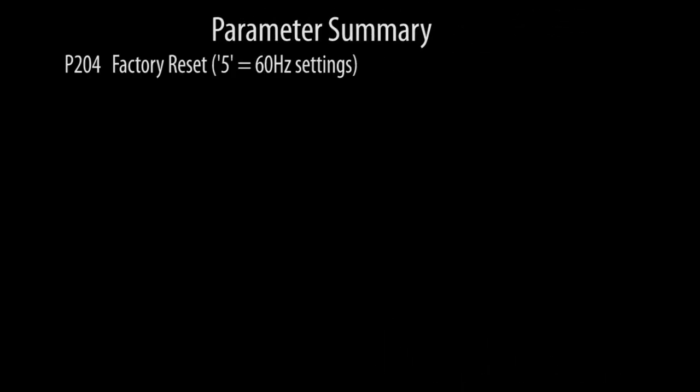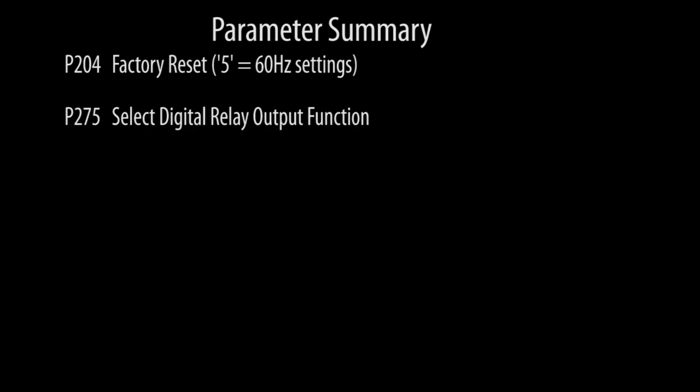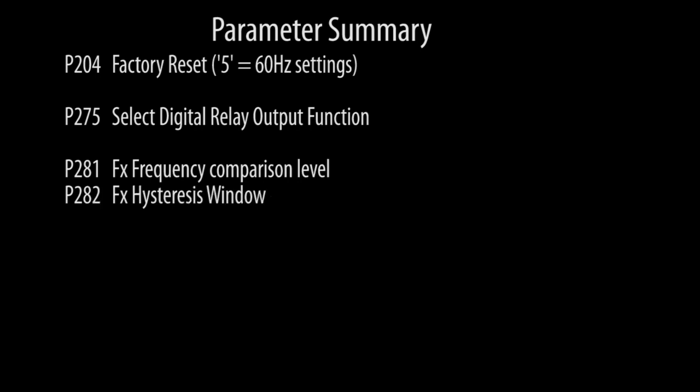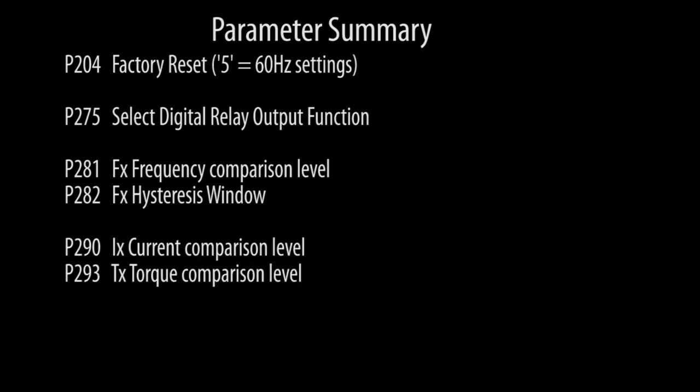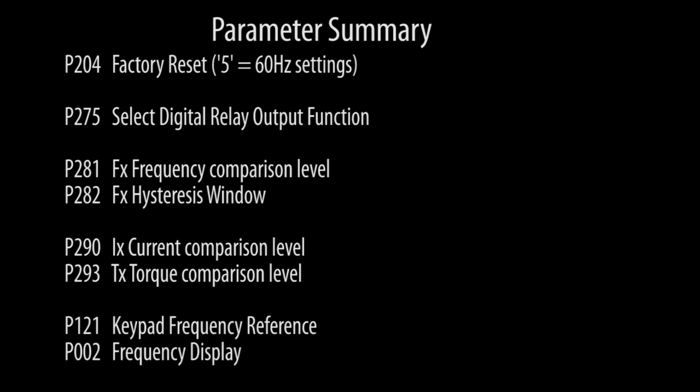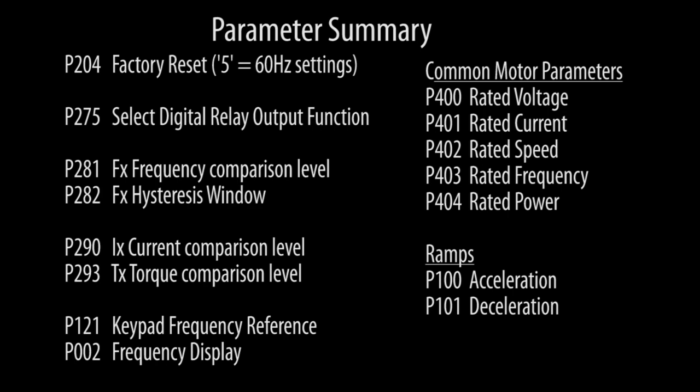So after the factory reset, all we really did was tell the digital output what we wanted it to do. For some of the functions we needed to provide a frequency level to compare against, and we found that we could even use hysteresis if we wanted to. There are similar comparison levels for the current and torque monitoring functions. While the default motor parameters worked for this demo, you should be sure to enter your motor parameters to get the best possible drive performance.